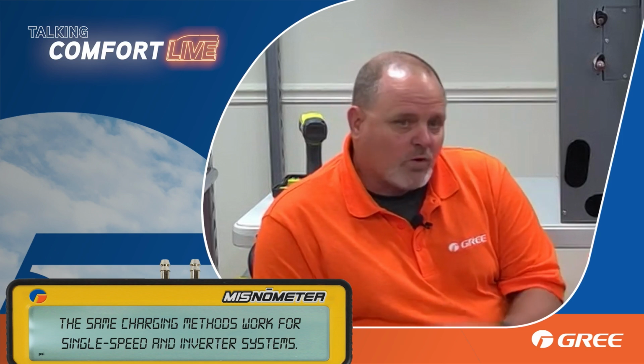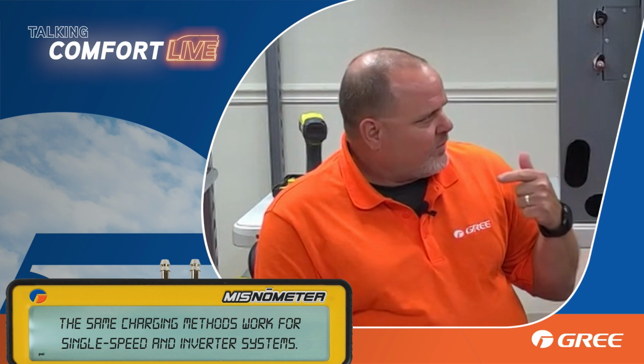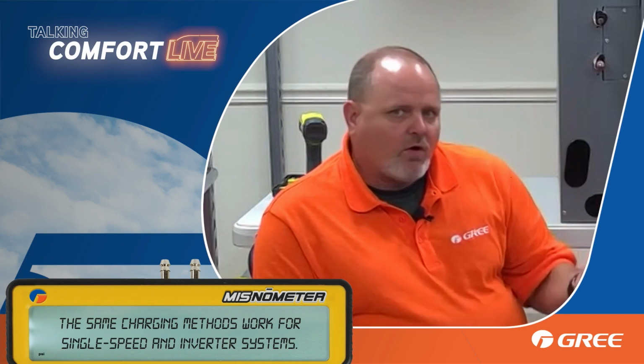And you're going to be best off recovering that refrigerant, weighing that charge back in. Because we don't have set speeds to it, the thing's going to do everything it can to save itself, unlike unitary product. It doesn't have that ability. That's one of the great advantages to the GREE equipment, is these things are loaded with pressure sensors, the thermistors, the board programming, EEV. All of these things that work together to protect that unit.